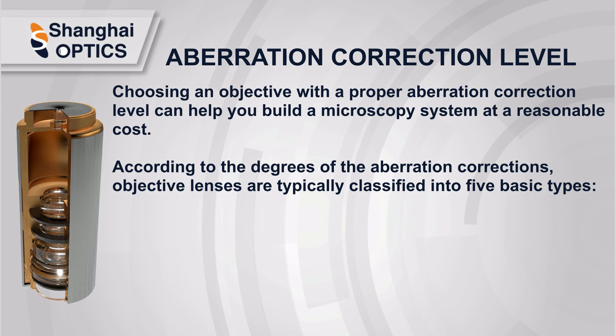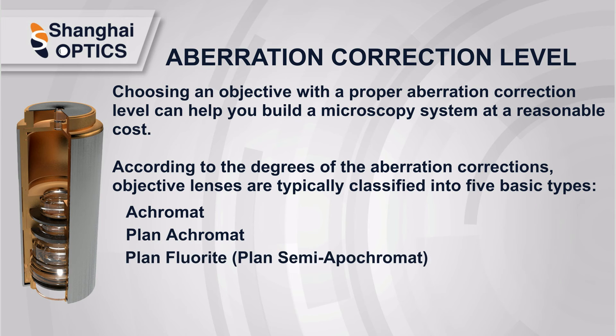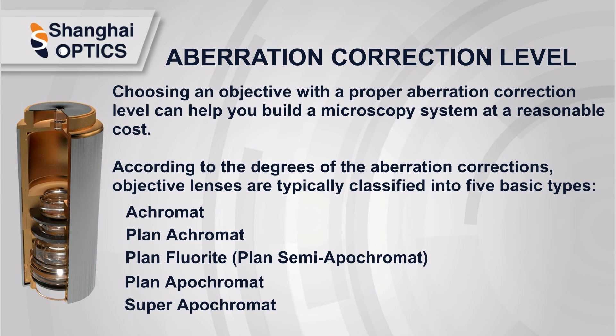The degrees of aberration corrections determine the optical performance of an objective lens. According to the degrees of aberration corrections, objective lenses are typically classified into five basic types: Achromat, Plan Achromat, Plan Fluorite, Plan Apochromat, and Super Apochromat. Choosing an objective with a proper aberration correction level can help you build a microscopy system at a reasonable cost.